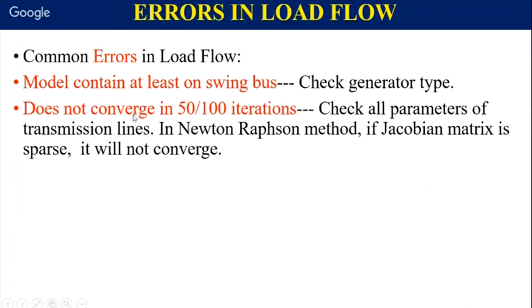Or sometimes you find that the load flow does not converge in the number of iterations you have mentioned. In that case, you have to check all the parameters of the transmission lines, even the parameters for active and reactive power and their limits. It is because load flow is calculated by MATLAB using the Newton-Raphson method.